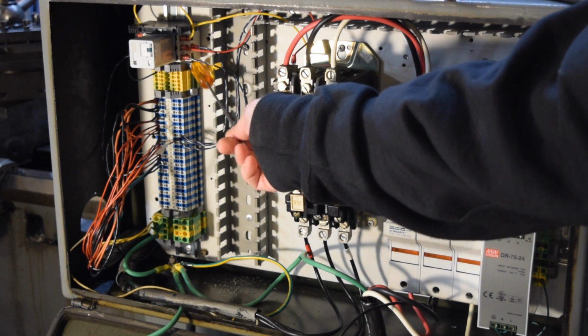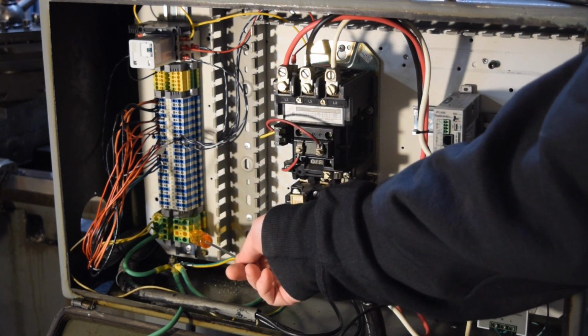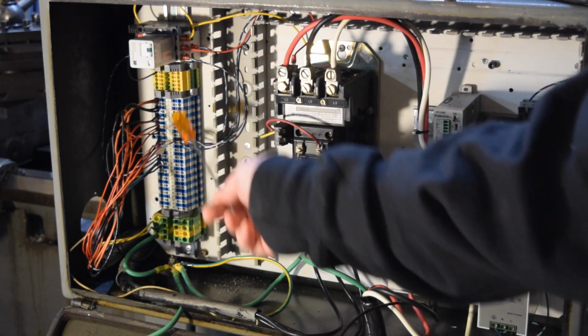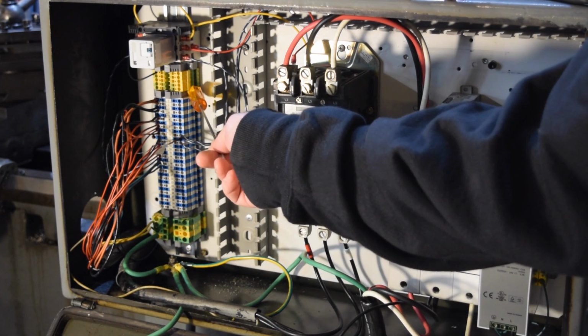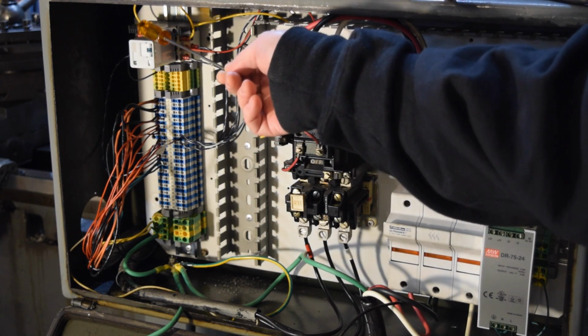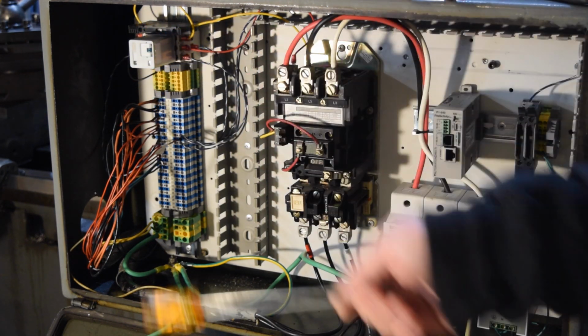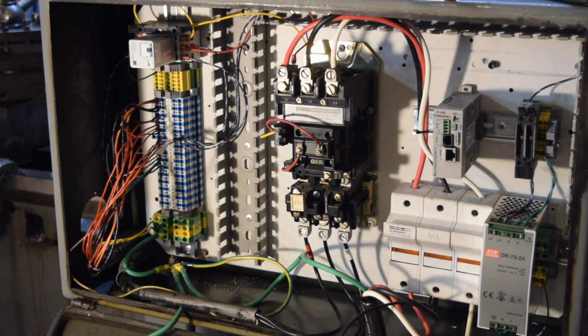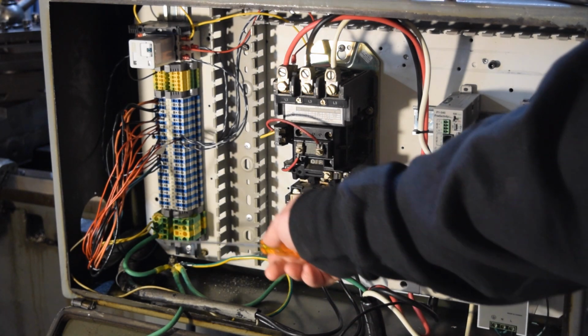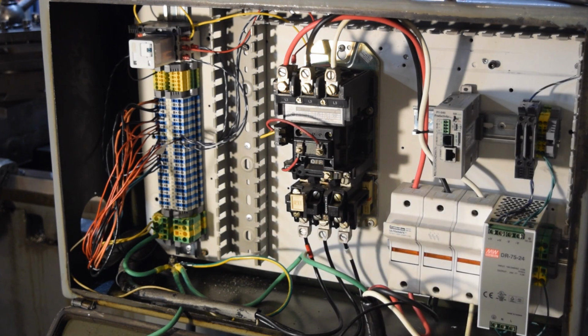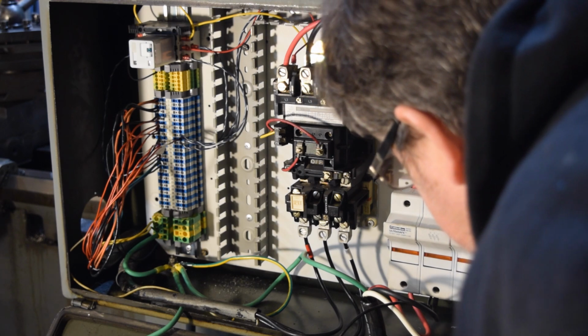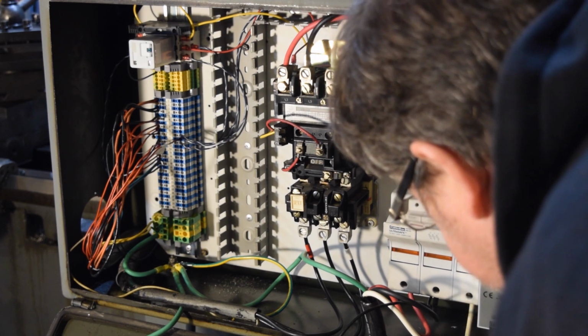Added some fuse blocks you see here. I mean, some ground blocks, some larger style. That's like a 4 or 5 millimeter. This is like a 2.5 millimeter. And an octal relay and a fuse here, and we'll explain that in just a second. I also replaced all of the internal ground wires and just in general cleaned things up. This contactor, it's a very common Allen Bradley 509 size. What size is this? I believe this is a size 2.